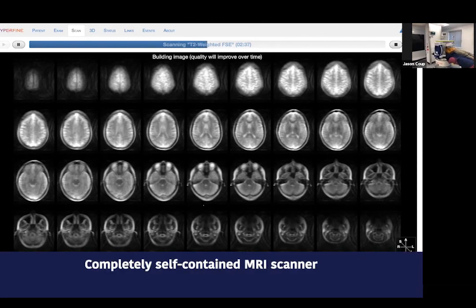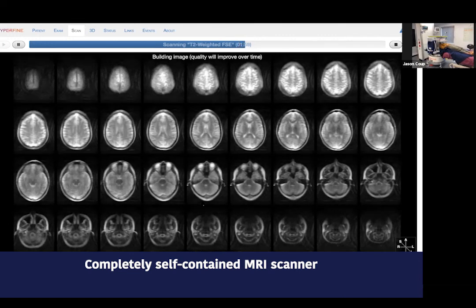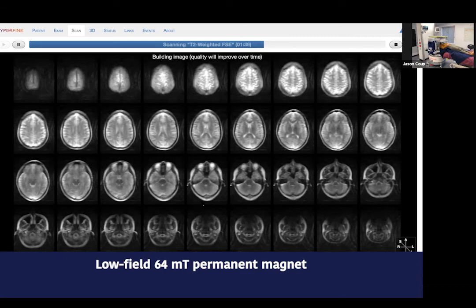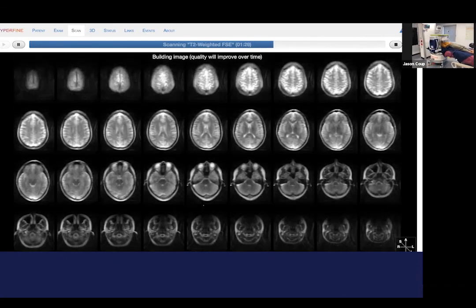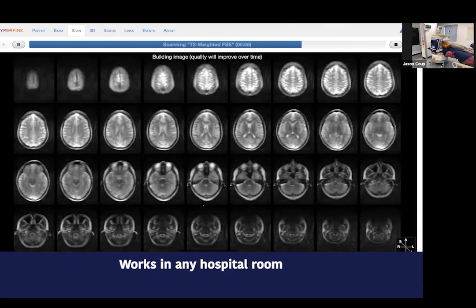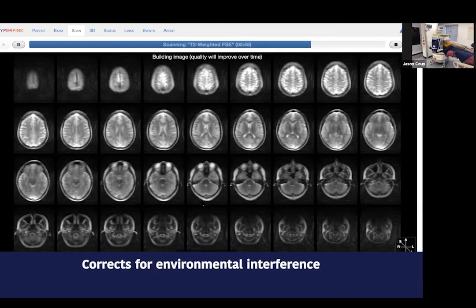Just to go over a few more details of this system, which is a completely self-contained MRI scanner. There is no equipment room associated with this system. Everything that you see in front of you is the system. There are no cryogens, no liquid cryogens. It's a permanent magnet that's always on, a low field 64 millitesla permanent magnet. This room is not a special room. It is not shielded in any special way. You can take this into any hospital room or any other room in the hospital, and it can deal with any surrounding equipment that may be nearby. You can see a patient monitor is powered up behind, has no impact on the image quality, and the scanner has no impact on the monitor.